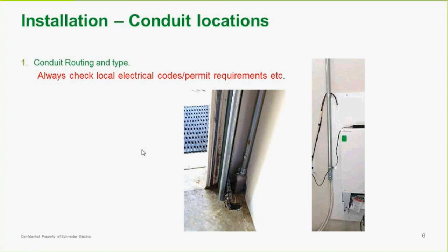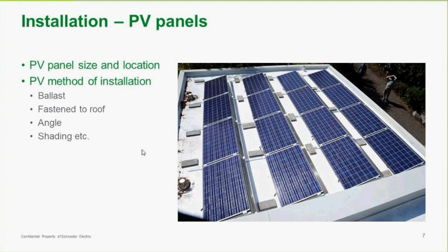There's all kinds of wiring and conduit that needs to be installed, and always ensure that you meet electrical codes, permit requirements, etc. There's the installation of the PV panels, and here we have PV panels installed on a flat roof, and this particular installation is using ballast, so there were no penetrations in the roof membrane whatsoever. And these little blocks are basically cement blocks, and they provide weight to hold everything in place. There's actually a wind screen that's behind these as well to prevent wind from getting underneath them and lifting them up.